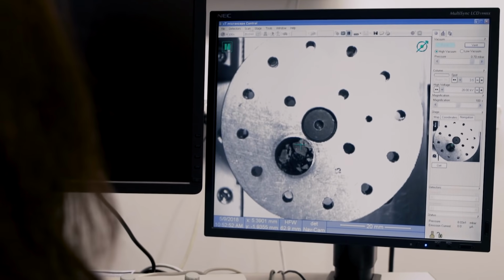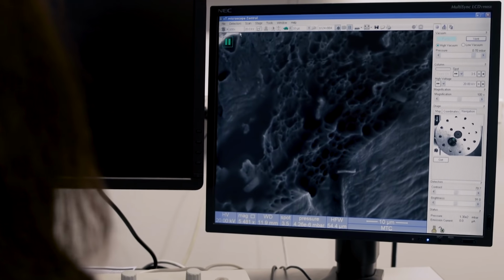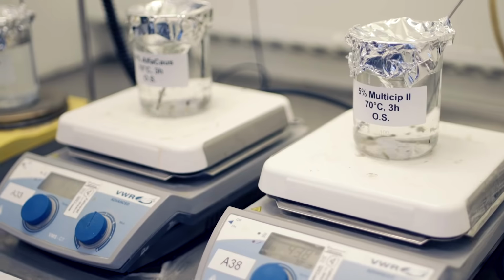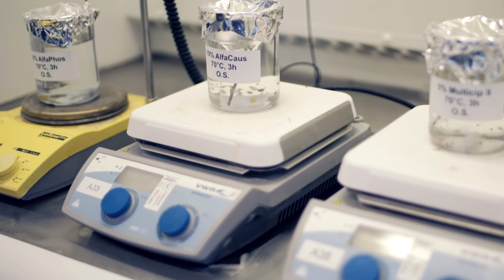Once we know what the fouling consists of, we will develop a cleaning protocol to dissolve it. It's very important to use the right cleaning chemicals, not only to achieve high cleaning efficiency, but also to prevent plate corrosion and gasket damage.